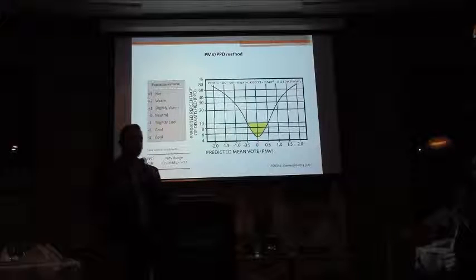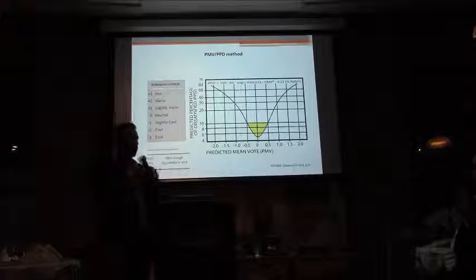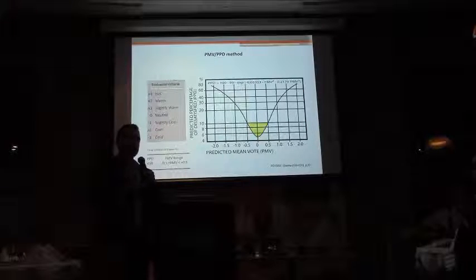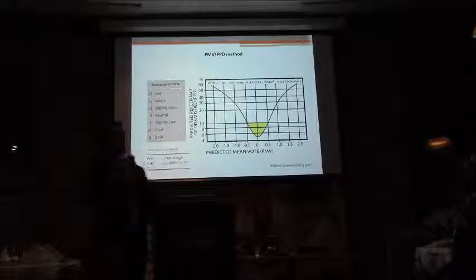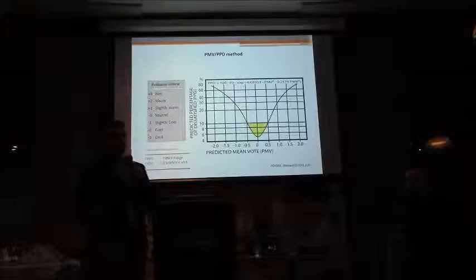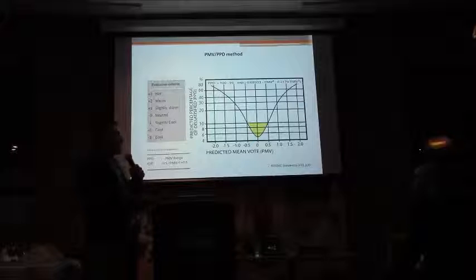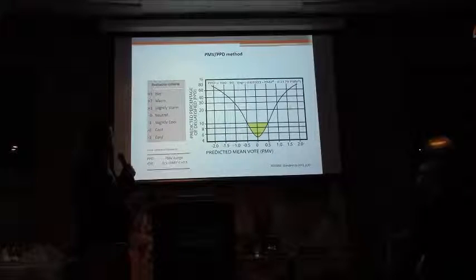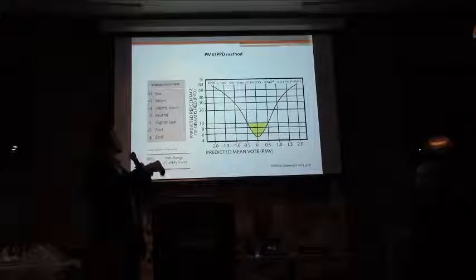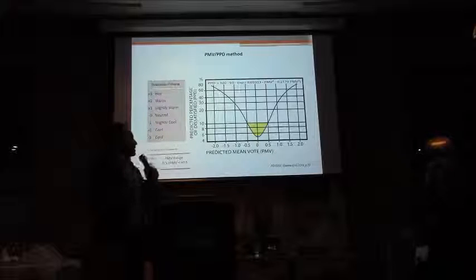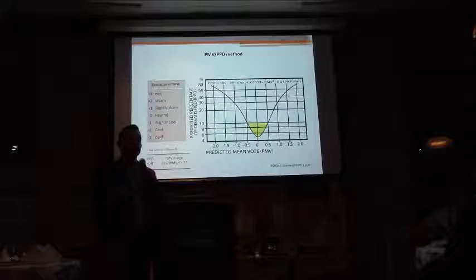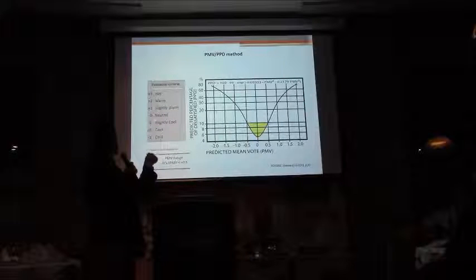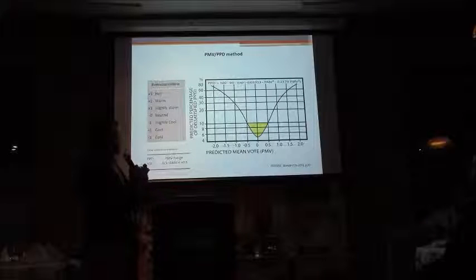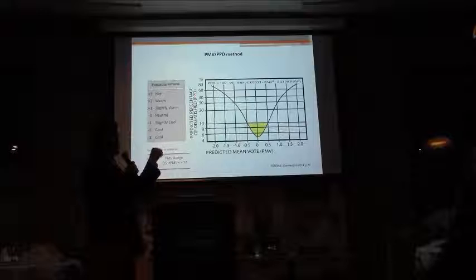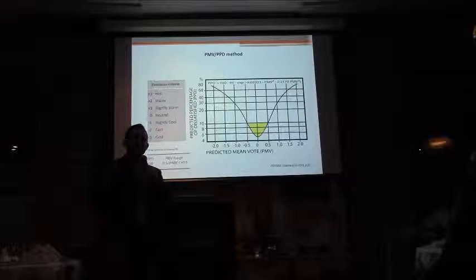So the way ASHRAE rated comfort is through statistical analysis. Basically, they took a group of people, put them in a room, and started subjecting them to different temperatures, humidity ratios, different velocities, different clothing, different activity levels. And every time they were subjected to a certain condition, they would ask the people to vote from -3 to +3. Basically, if you're at -3, you're too cold, -2, you're cold, all the way up to +3 where you're just too hot. Anything that's +2, +3, or -2, -3 is considered a fail for ASHRAE. So you have to be between -1 and +1 to pass.